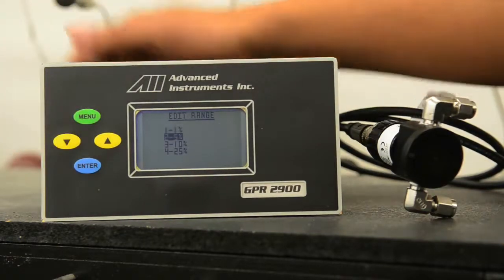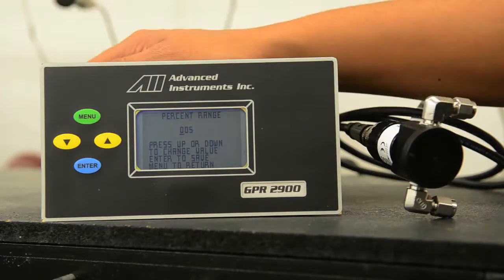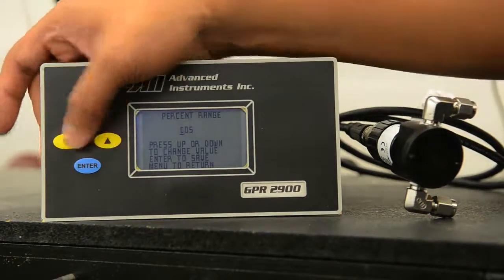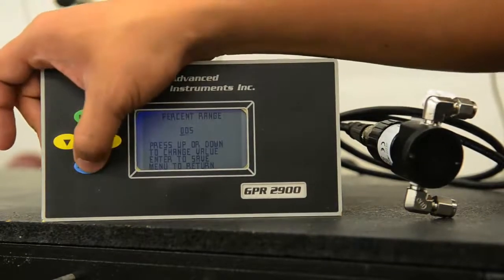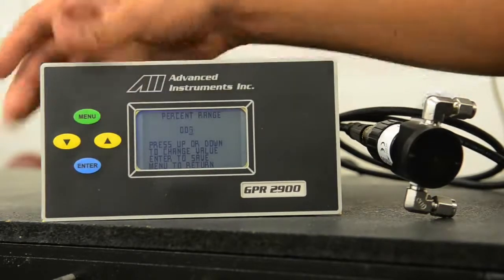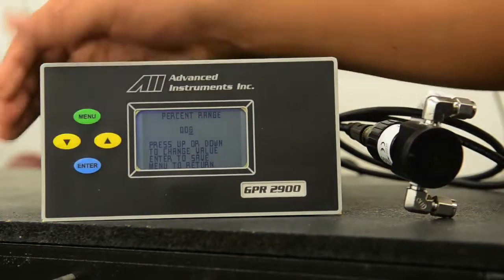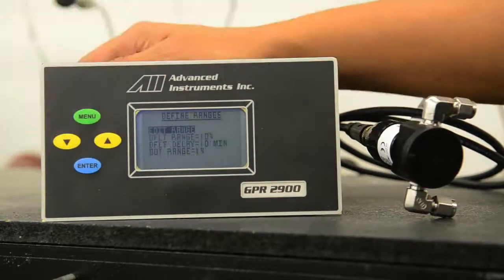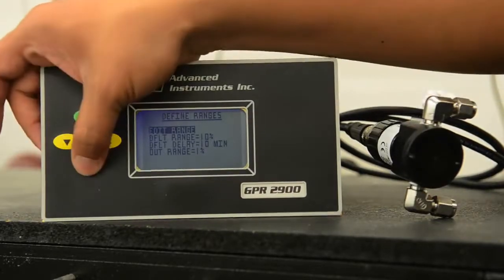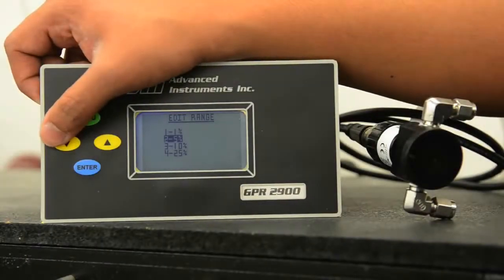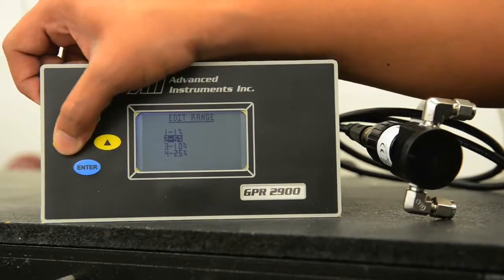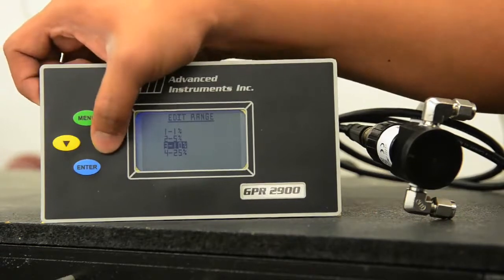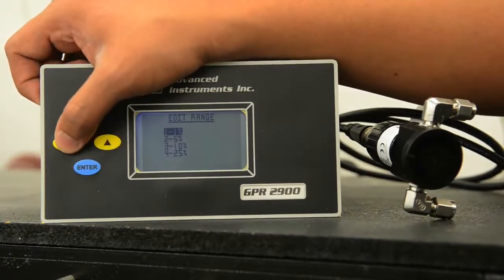And if we go to the 5% range option and select enter, we are taken to the screen where we could adjust the value of the range using up, down, and enter. We like to set it to 7, or we can set it back to 5. Select enter, and that value is saved under the Edit Ranges options, as you can see there. This is ideal to match your 4 to 20 output with a certain range of interest that you would like. Again, all 4 ranges can be changed. However, do note that your lowest range cannot be over the next range above.